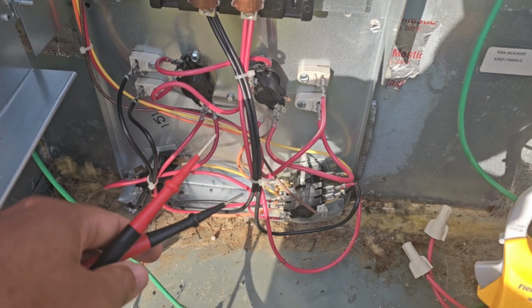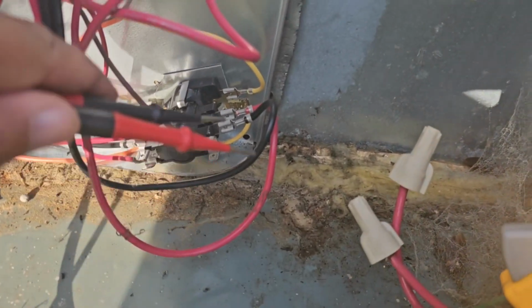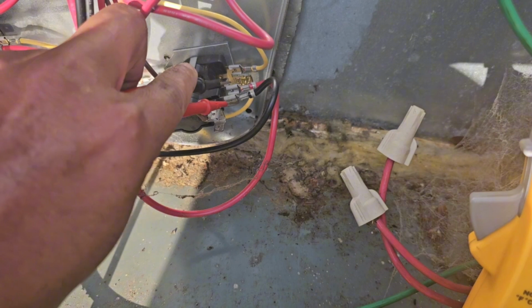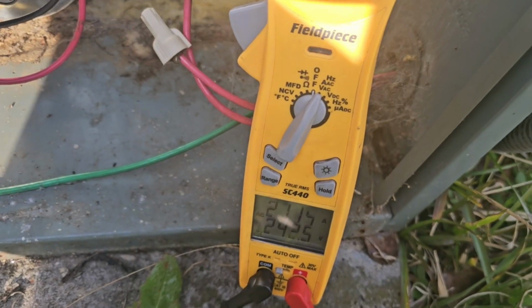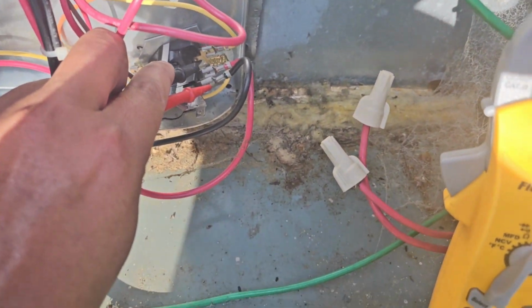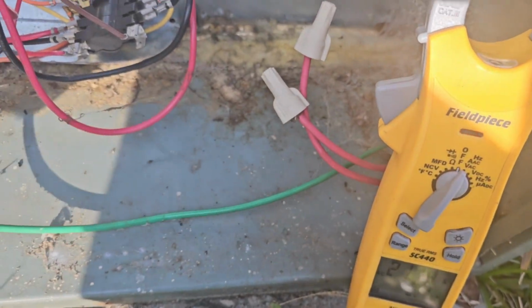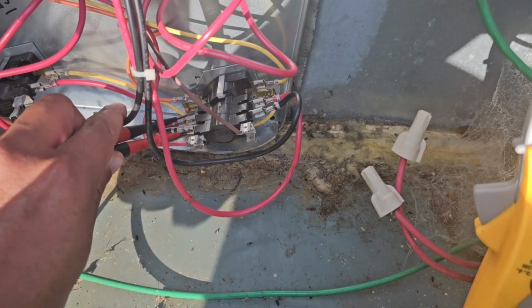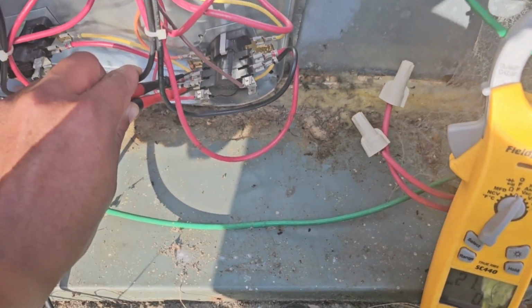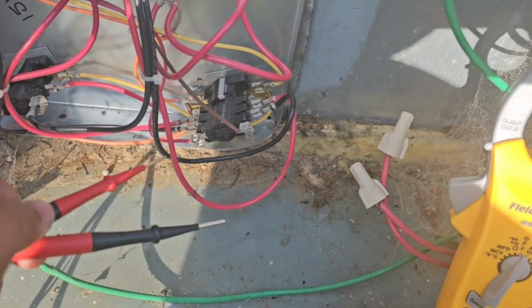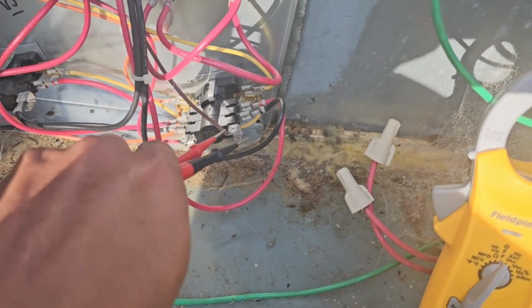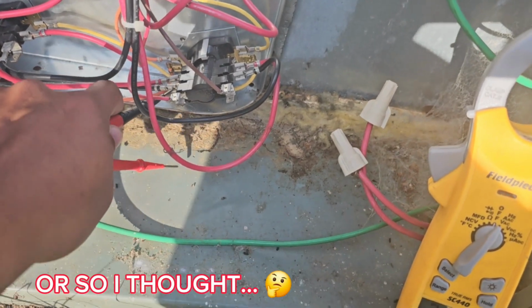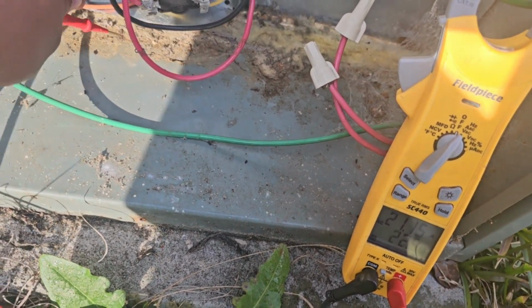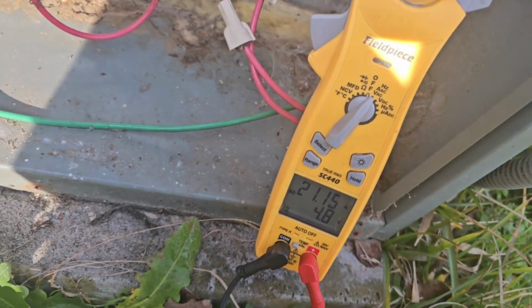After deep diving into this for a bit, I'm finding out that right here, where I'm supposed to get 240 because it's two opposite legs of power, I do get 240. However, if I go to the other side, I'm at 0. And I know this heat sequencer is pulling all the way in, because from each of these to ground... well, that's a weak ground, hold on.